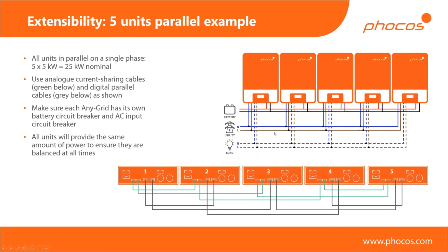So what's important for you is that they must all be on the same battery. You cannot have multiple batteries with these inverters. They will throw up an error if you do try that, and there's very few cases where I think that would make any sense. You also need to have breakers for each unit individually, just for the sake of safety.